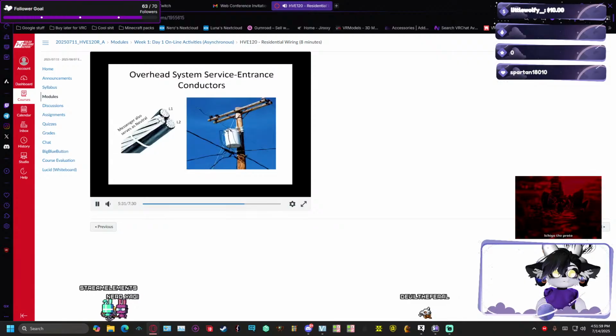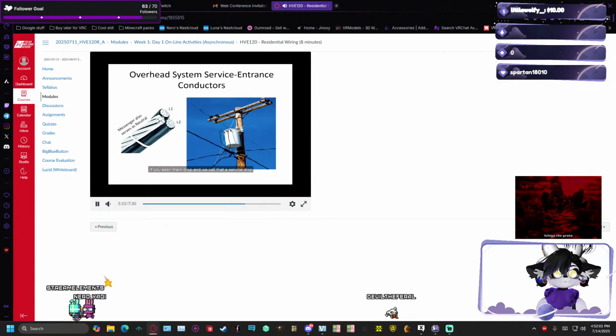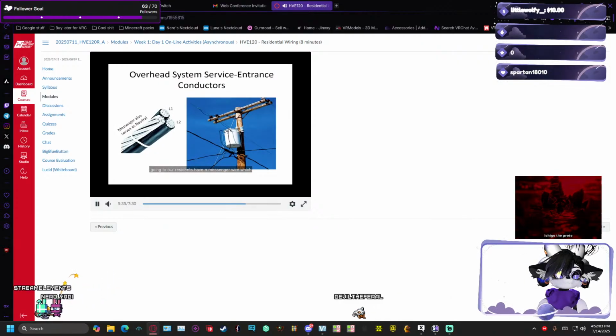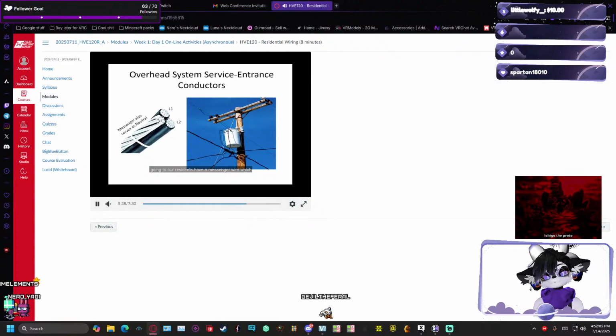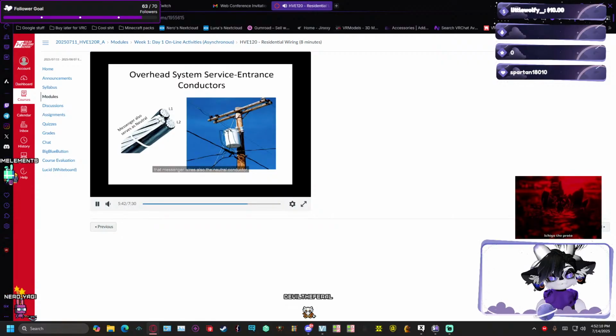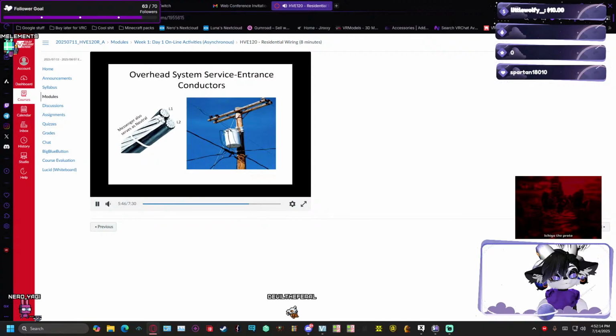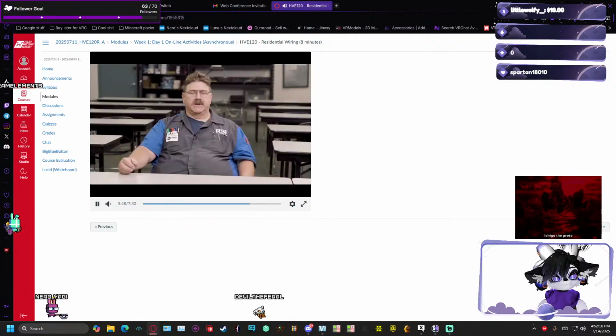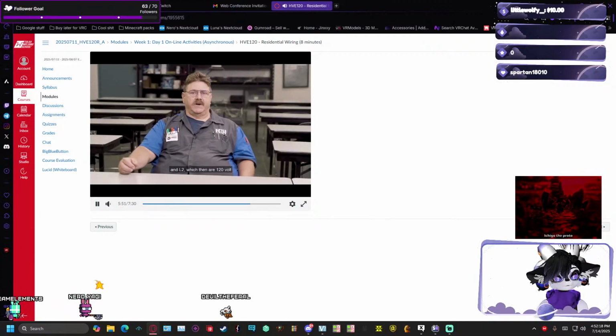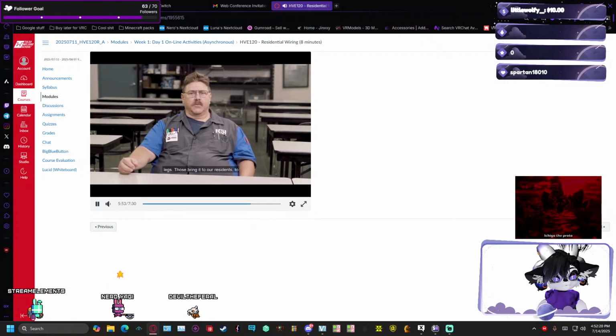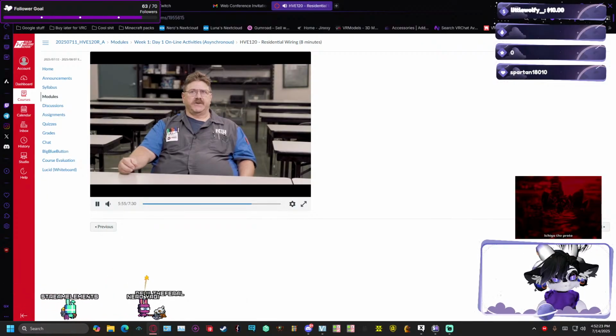Overhead system entrance conductors, if you've seen them drop, and we call that a service drop going to our residence, have a messenger wire which supports the conductors coming down from the pole. That messenger wire is also the neutral conductor. So we'll have the messenger as the neutral, which is our bare conductor in the drop, and L1 and L2, which then are our 120 volt legs. Those bring it to our residence.